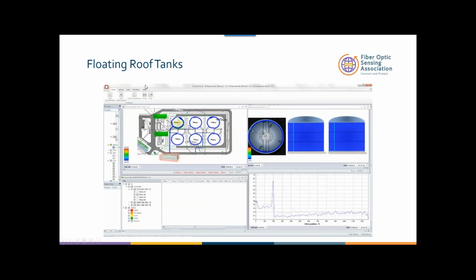Here's an example of why it's very important: you can also look at the other tanks, the adjacent tanks, and be able to flood the other tanks before these other tanks are affected by the tank on fire. In this case, the software is showing exactly that. So if there is a high temperature at this location, you can flood this tank number 2, and then you can flood tank number 3 as well to make sure that the fire is not expanding.